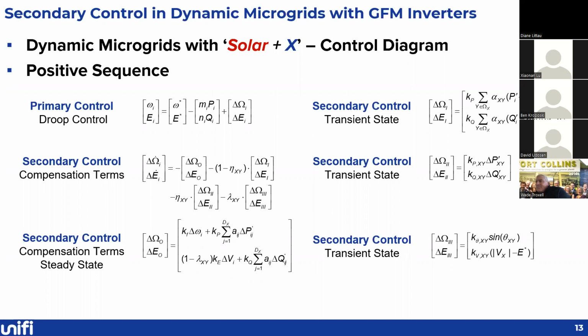the through active power and reactive power. For example, when we need to open the switch, we need to minimize the through active and reactive power first so that we can safely open it. On the other side, when we need to close the switch, the resynchronization efforts are also considered and incorporated into the secondary control level as one of the compensation terms.